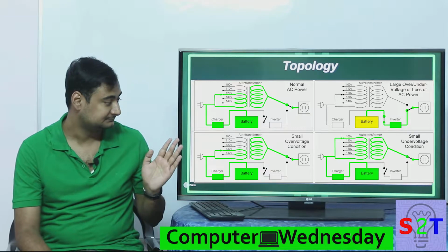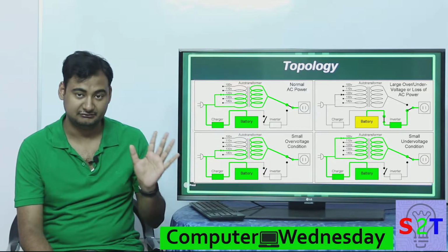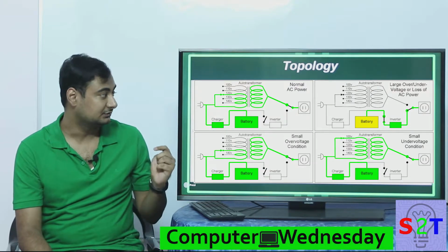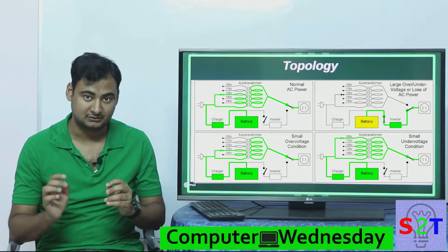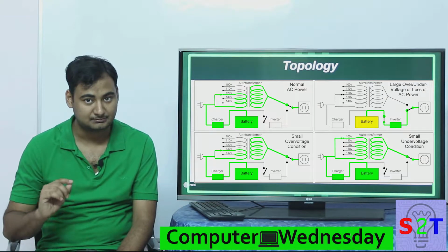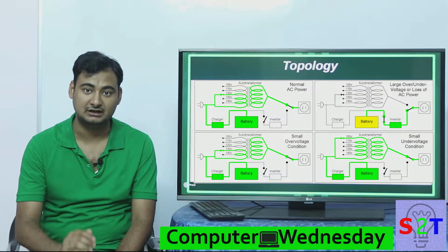So we have to understand this topology is that it's not a standby device. It's not completely deactivated when you turn it off. It's using itself whenever you are connecting anything to it. So this has what's called an auto transformer. Basically what that means is that many of you have seen that a UPS does not allow power to flow through it if you have turned it off.